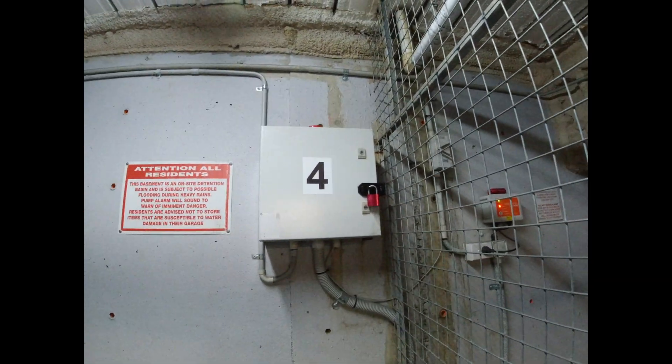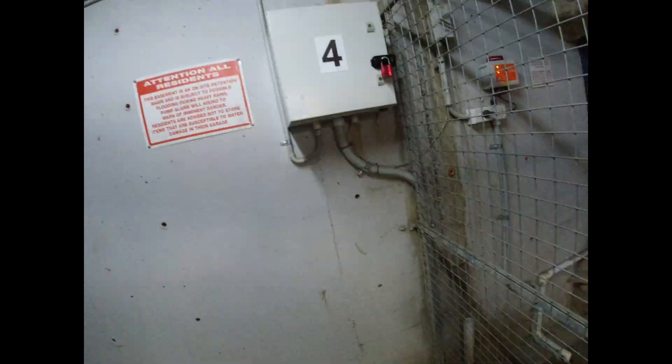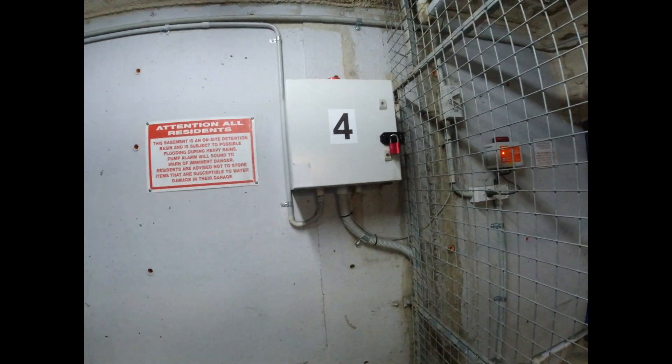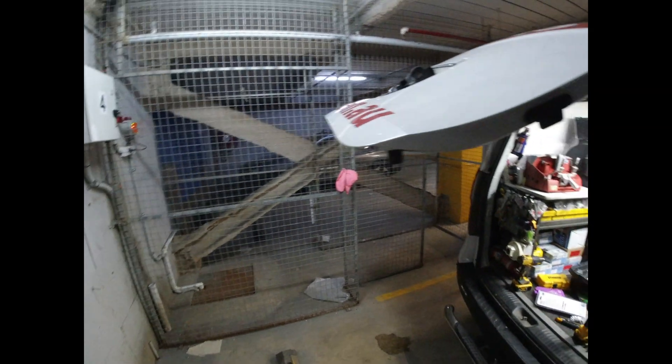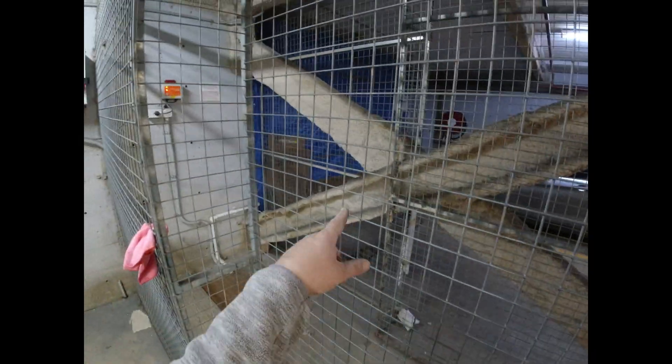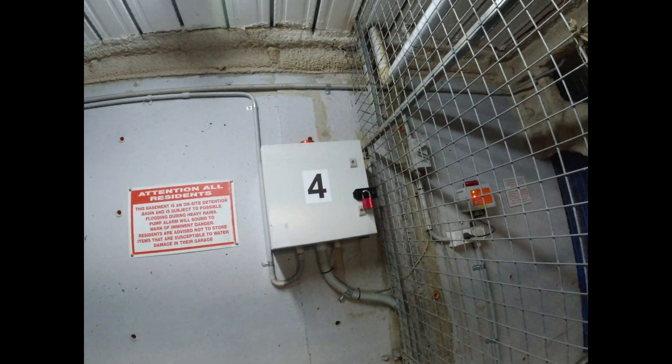That will prevent people from being able to tamper with it and turn it off, so they can't bypass the alarm — meaning the pumps will still work. If there's any water issues the pumps are ready to go, because failing to get rid of the water leads to massive problems: flooding, loss of cars. I've seen in some that they can flood up, especially with the weather we're having — a lot of water sometimes. You can see rust up here; I wouldn't be surprised if water has come all the way up here judging by that. So, installing a hasp staple on a water pump cabinet — that's all I've got today. Thanks for watching!